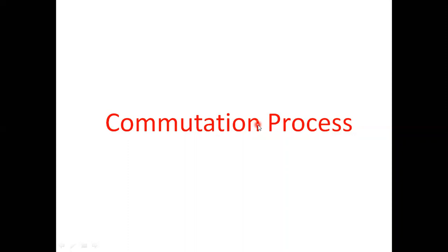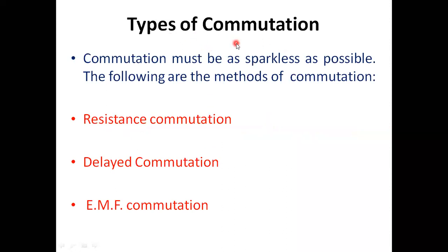In this video we will discuss the commutation process. Commutation is the reversal of current in the armature coil when it passes the brush. The brush makes the coil short-circuited, and during this process the current flow in that particular coil is reversed. We will discuss different types of commutation. Our aim is to improve the commutation process so that there is no sparking and no damage to the brush or commutator segments.